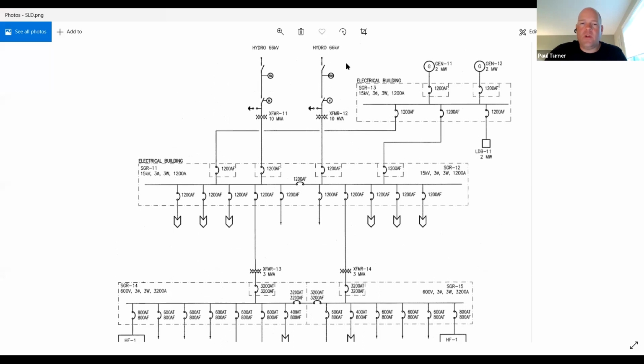So I'll briefly go through each component here and the general startup philosophy. During pre-commissioning, all of these systems would be unenergized, or at least the bus voltages are unenergized. Switchgear would be energized at the control level with the 15 kV bus de-energized and everything subsequent down there. During pre-commissioning is when you can test a lot of the alarms to the HMI, PLC controls, as well as interlocks of each particular piece of equipment. Once that's completed, you're ready to start up the system.